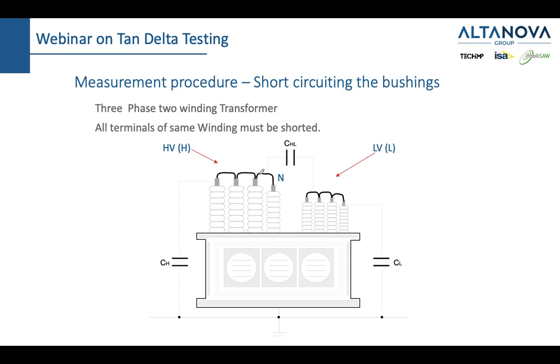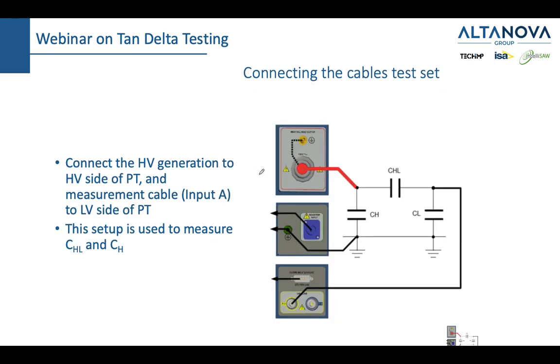And you can do this with a thin wire, because the current flowing will be milliamps. So you don't need to use thick wires. Of course you can, but it's not necessary. With this setup, as you can see, generation on the high voltage winding and measurement on the low voltage winding, you can measure CHL, which is this one, and you can measure CH. Using this setup, you cannot measure CL. To measure CL, we'll do something else.